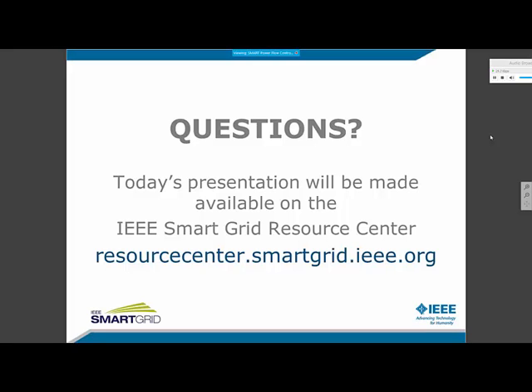Okay, thank you. What type of switches are used in the UPFC inverters, and how are they triggered? The one that I just mentioned, the inverter-based UPFC, which is one way to build a UPFC, uses controllable switches. And I mentioned it. What is a controllable switch versus an uncontrollable switch? A thyristor is an uncontrollable switch. Once you turn it on, it naturally turns off. But with a controllable switch, you decide when to turn it on and when to turn it off.